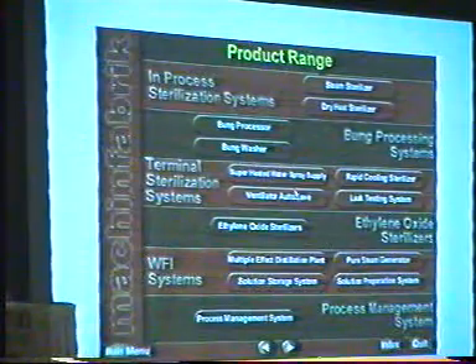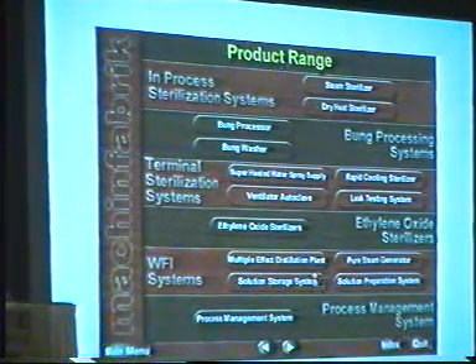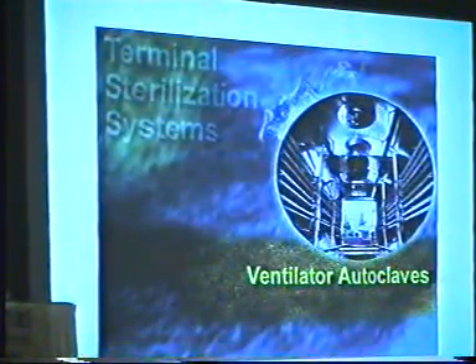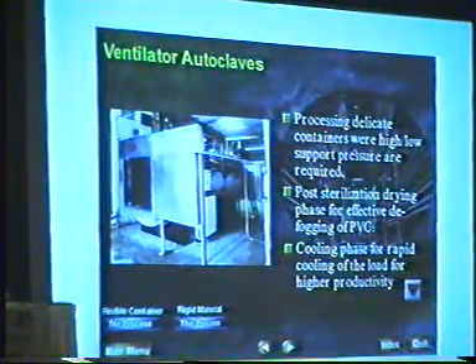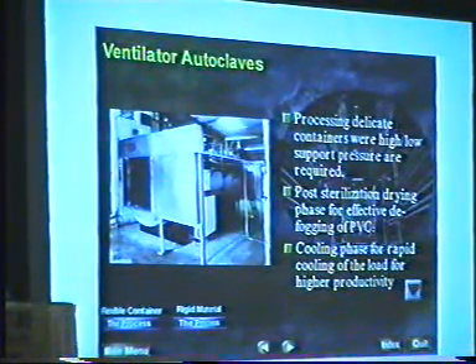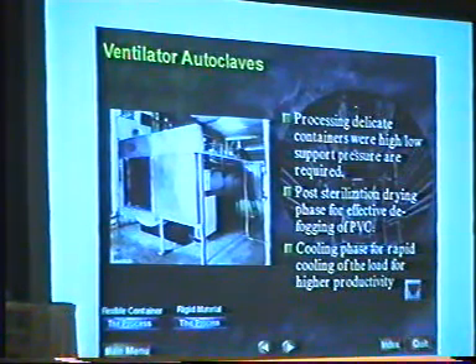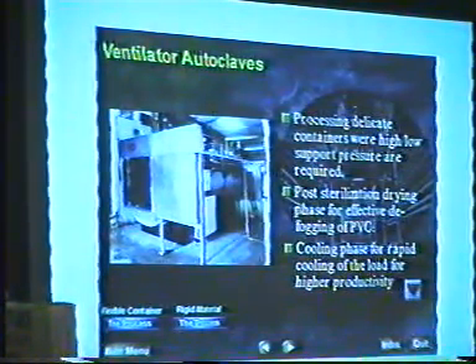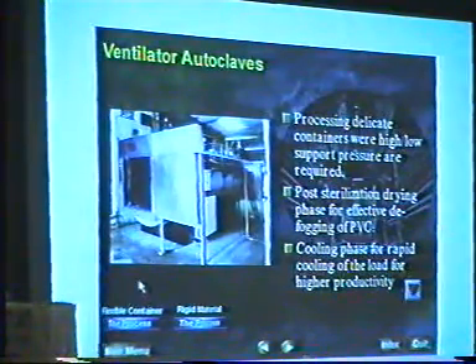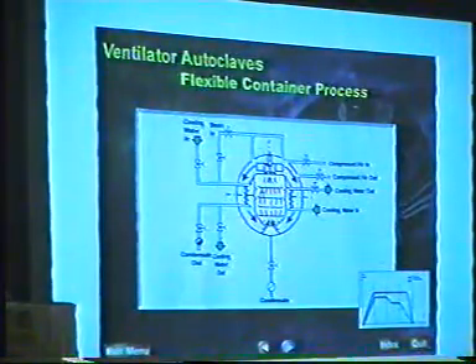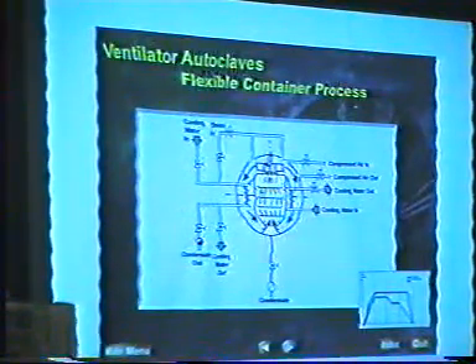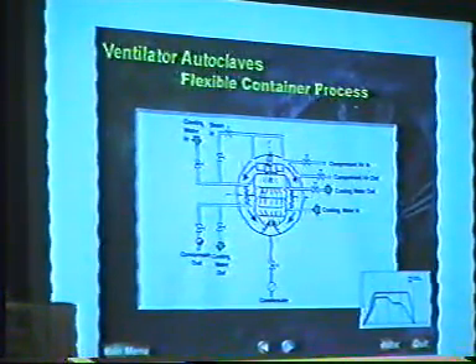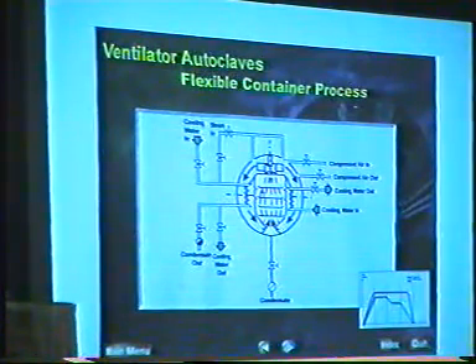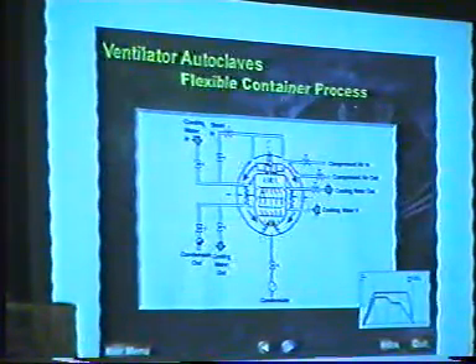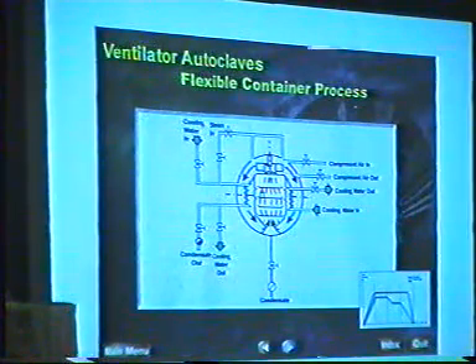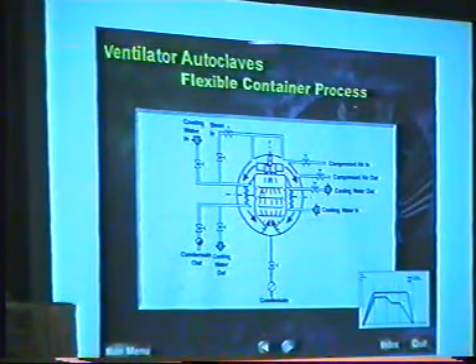After superheated, I will briefly come to ventilator autoclave, which is equipment used for isothermal sterilization. Here also, instead of saturated steam, a mixture of air and steam is used as a sterilizing medium, and the classical relationship between pressure and temperature is broken. Similarly, air removal does not mean anything to this process. However, in ventilator you have to introduce steam, so you cannot use plant steam and you have to buy an additional pure steam generator.